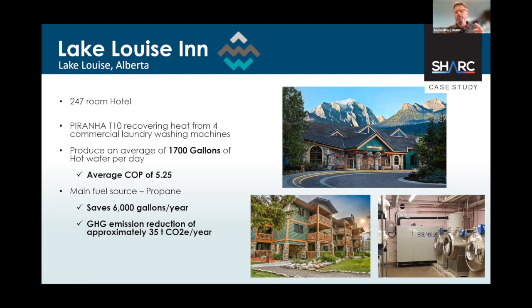And the manager of the hotel told us that prior to the piranha going in, his hot water boiler would have to cycle like every 5 minutes. We're now getting it to about every 35, 40 minutes it has to cycle. And as you can see, with a COP of over five, we're saving them 6,000 gallons of propane a year. I don't know what you guys pay for propane, but it's a massive savings for the hotel, and again a large GHG CO2 reduction as well.